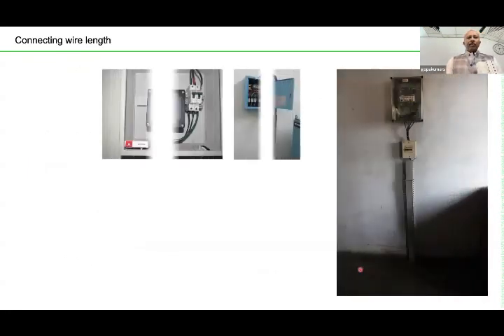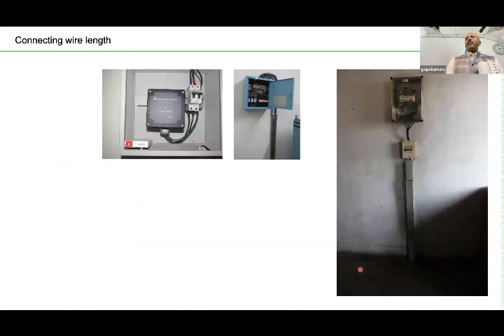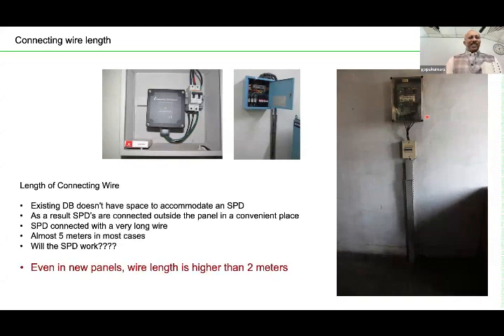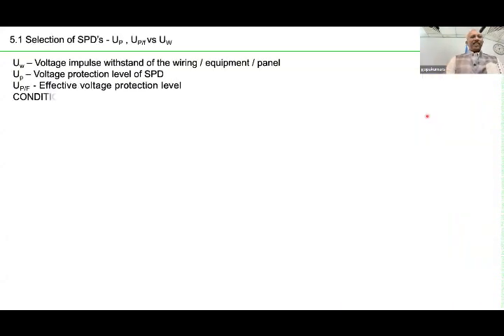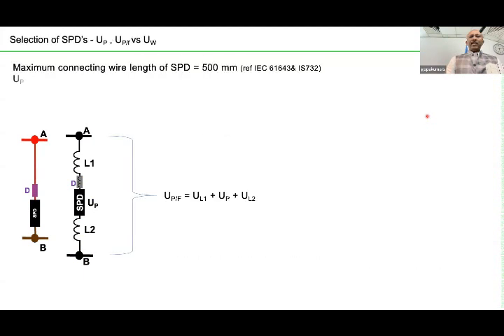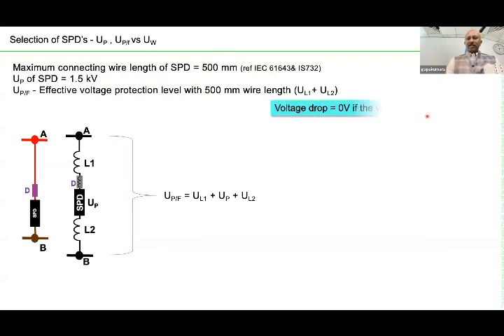Now, most of the time you see SPDs connected in this fashion. In the first case here, this is in an airport. The recommended connecting wire length is 500 mm, and the actual wire used is about 5 meters. So I would say this SPD is a showpiece. People will look at the SPD and say, aha, I am protected until the next lightning. Otherwise, it won't do any job. So this subject is very, very important. I have some calculations, but let me skip those.